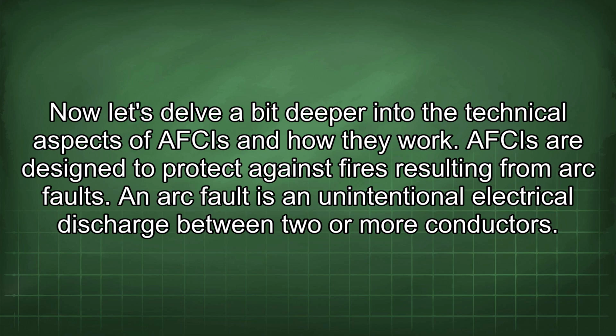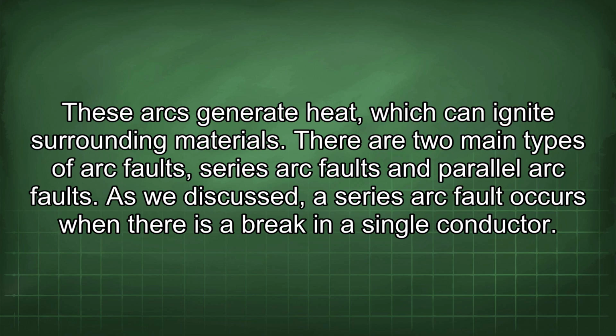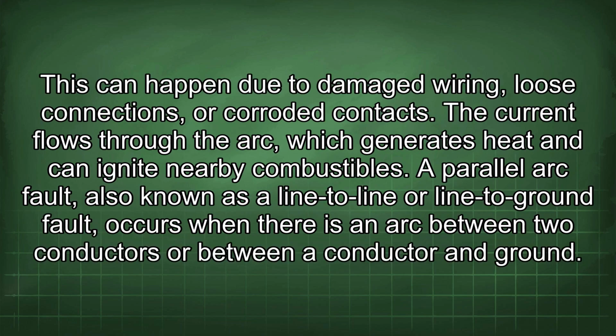AFCIs are designed to protect against fires resulting from arc faults. An arc fault is an unintentional electrical discharge between two or more conductors. These arcs generate heat, which can ignite surrounding materials. There are two main types of arc faults: series arc faults and parallel arc faults. As we discussed, a series arc fault occurs when there is a break in the single conductor. This can happen due to damaged wiring, loose connections, or corroded contacts. The current flows through the arc, which generates heat and can ignite nearby combustibles.